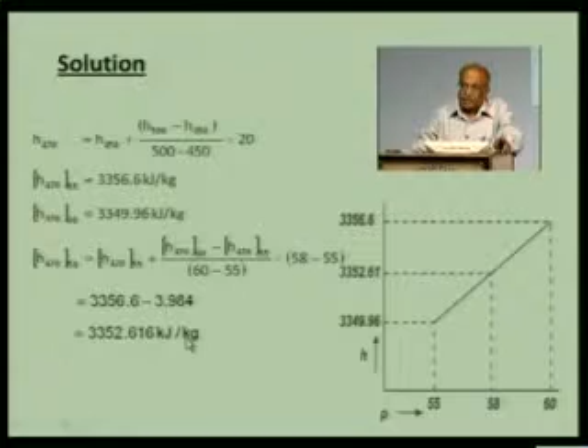The Mollier chart consists of a constant pressure line of 60 bars and a constant pressure line of 55 bars, right, and there is a temperature line of 450 degrees centigrade and 500 degrees centigrade. These lines are available on the Mollier chart. Now, we have to calculate the enthalpy at 58 bars. So, let us draw a line of 58 bars between 55 and 60 bars as shown by the dotted line here. Again, the temperature of 470 is not available in the Mollier chart, but 450 and 500 temperature lines are available. So, we can plot a temperature line in between 450 and 500 degrees centigrade, which would represent a value of 470 degrees centigrade.